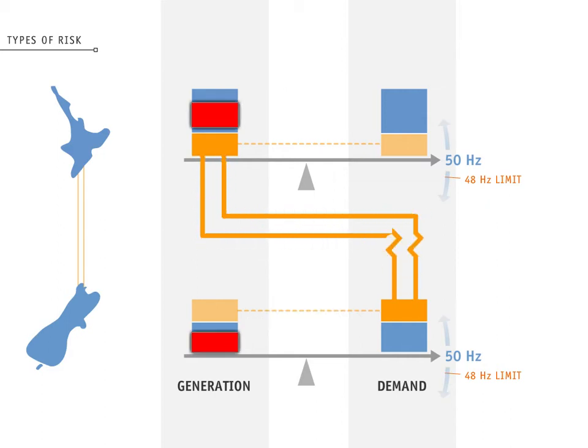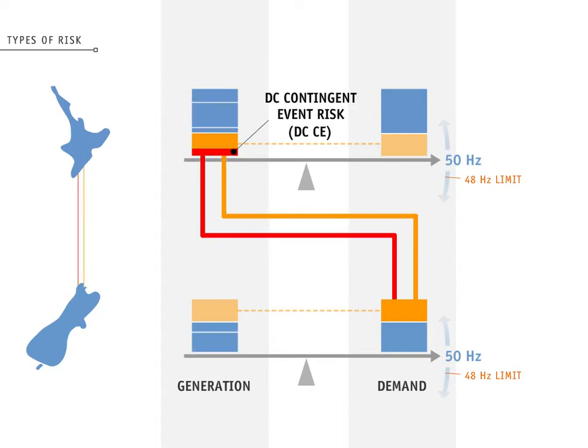The North and South Islands have independent AC risks. When both HVDC poles are in service, a DC contingent event, or DC-CE, is defined as losing a single HVDC pole. If this happens, more power can normally be put on the remaining HVDC pole to help compensate for the loss.